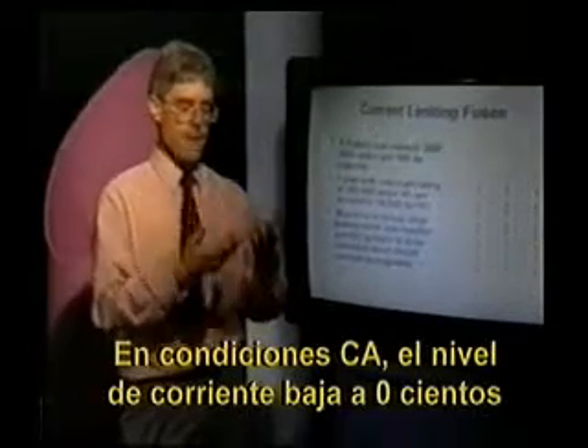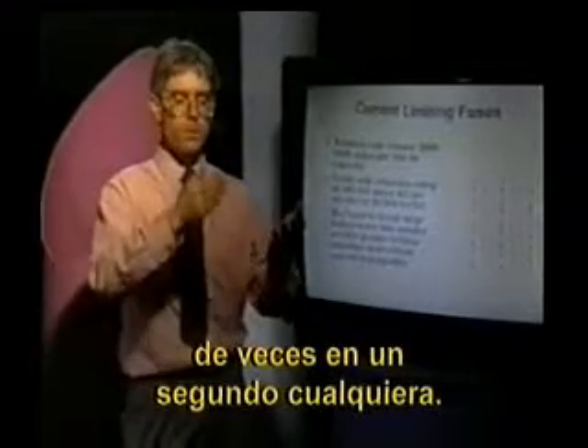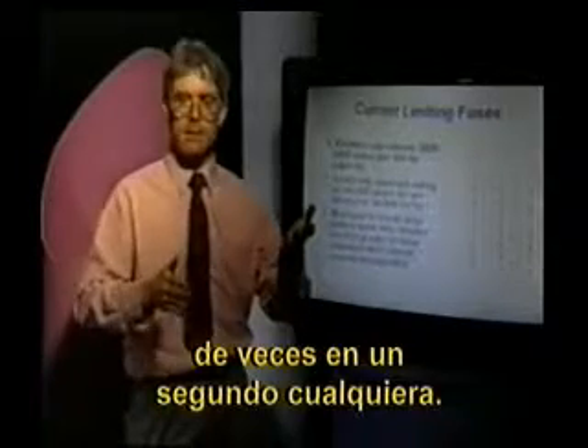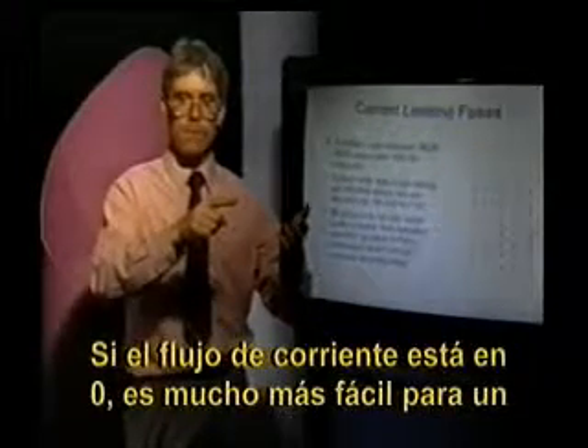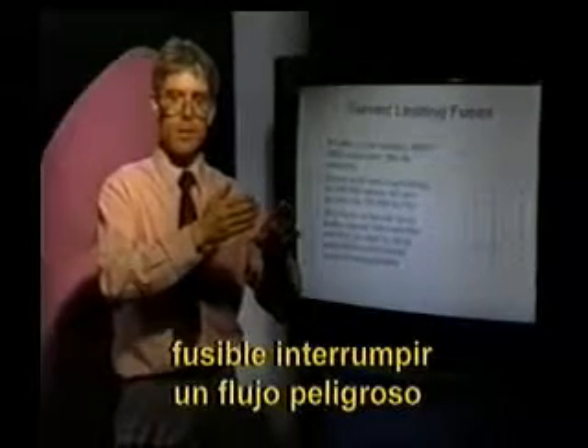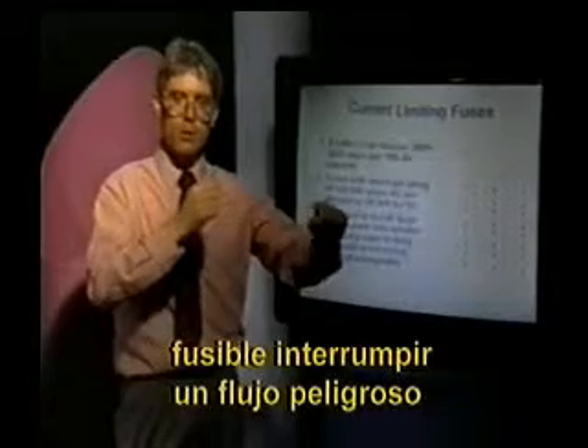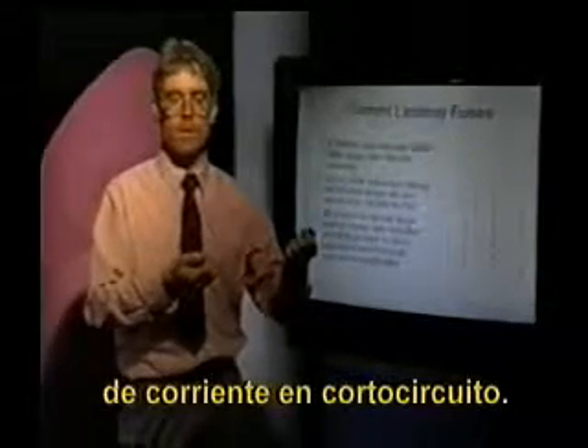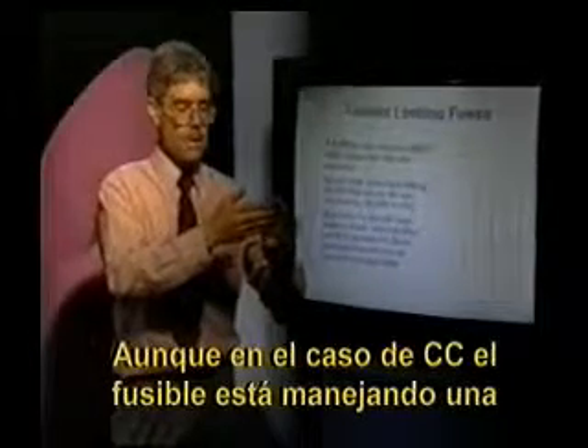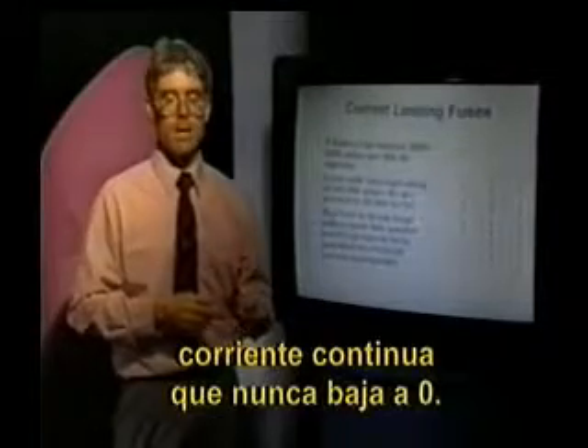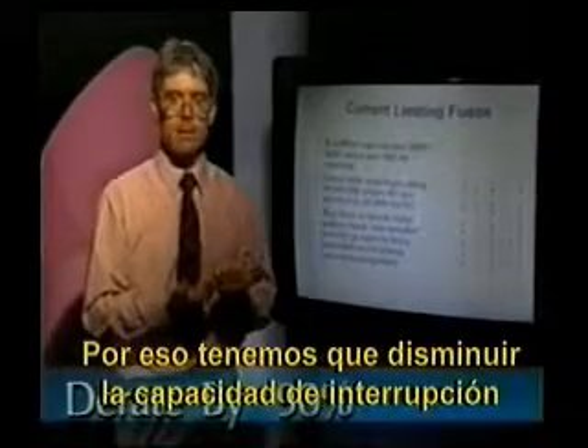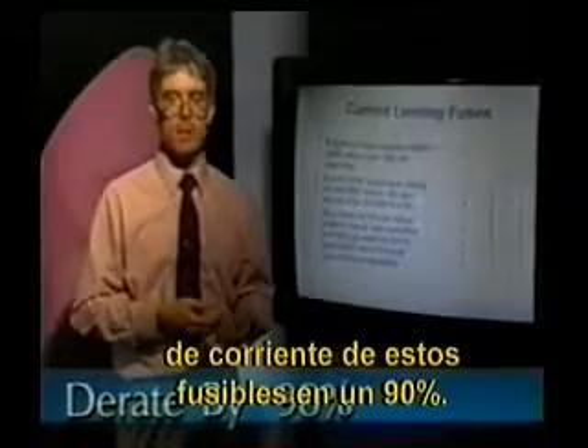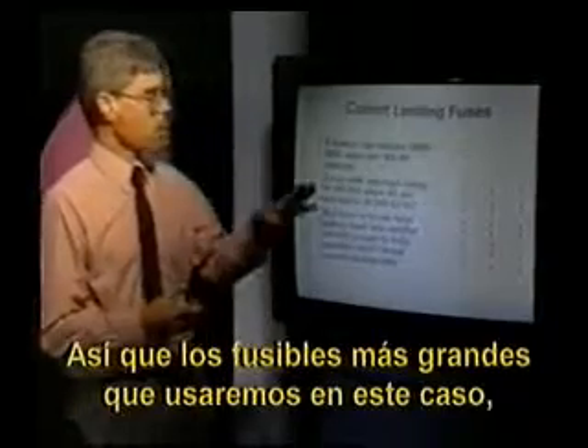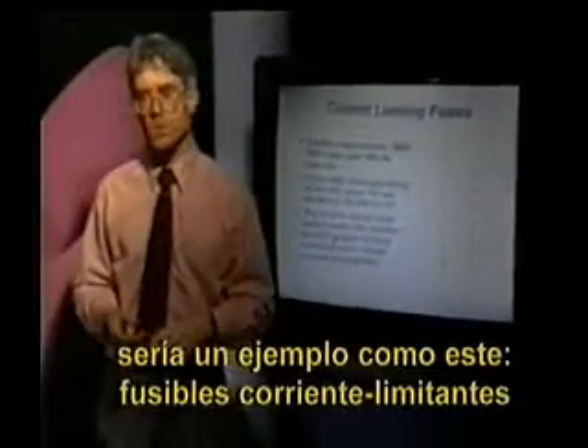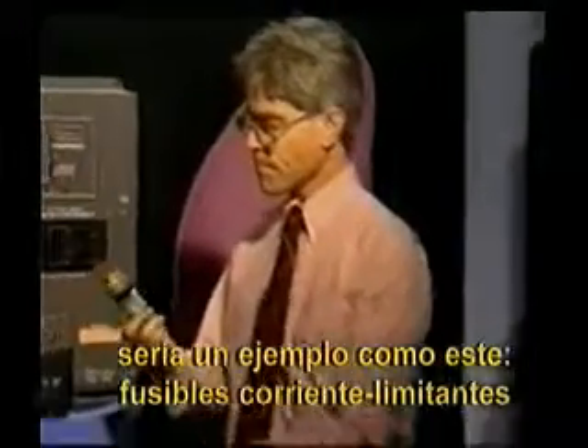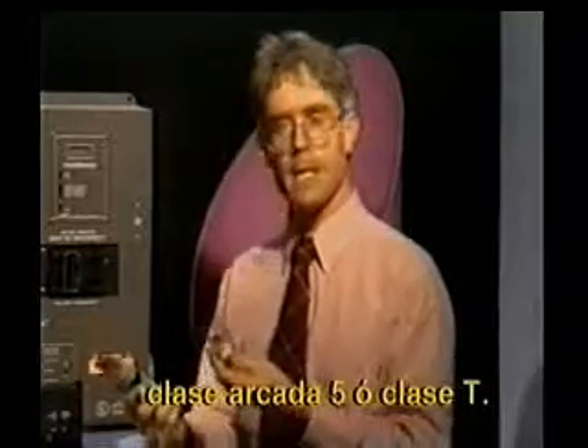In the case of AC conditions, multiple or hundreds of times in any second, the current level actually goes to zero. And if we're trying to break a dangerous short circuit current flow, and the current flow actually goes to zero, that's much easier to break, much easier job for a fuse to do. In the case of DC, though, the fuse is handling a continuous current that never goes to zero. Because of this, we have to derate the current breaking capability of these fuses by 90%. So the largest type of fuses that we might use in this case, these current-limiting fuses, would be an example like these, Class RK5 or Class T current-limiting fuses.